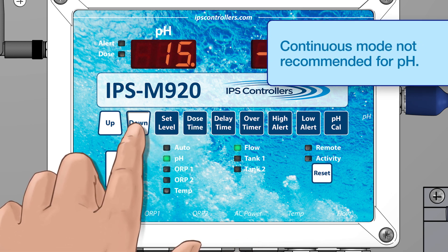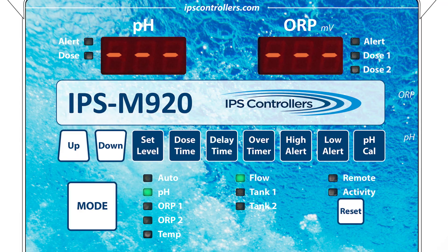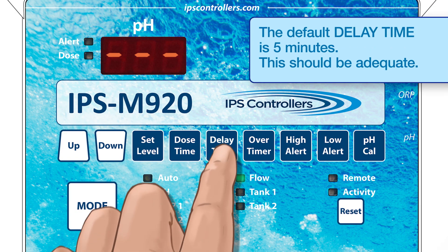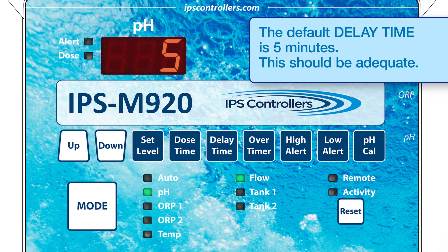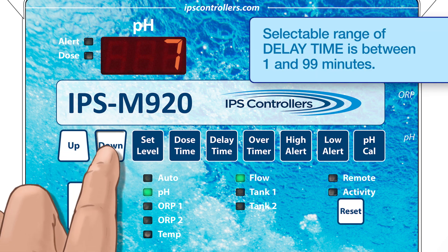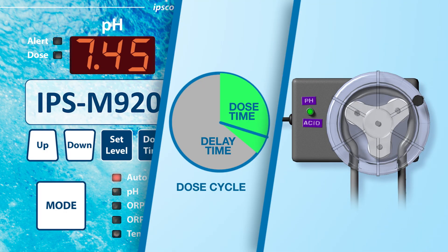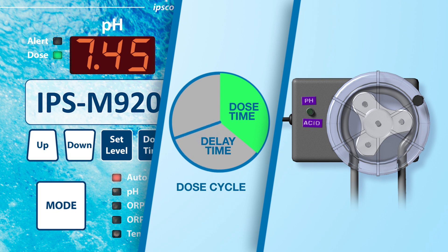It is possible to select a continuous dose time, but it is not recommended for pH. In the Delay Time function, if you have chosen a timed feed, the default is a delay time of 5 minutes between feed cycles. The selectable range of delay is between 1 and 99 minutes between feed cycles. After the dose time has been reached, the controller will de-energize the pH output for the selected number of minutes before checking the current level and dosing again if necessary.